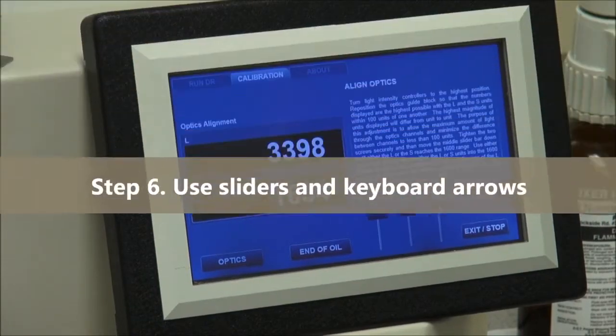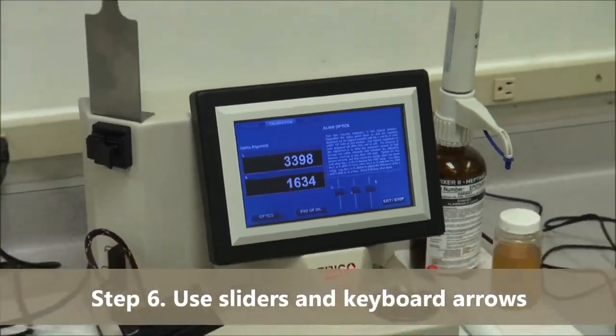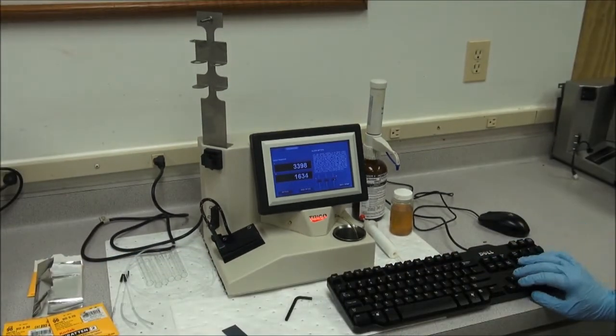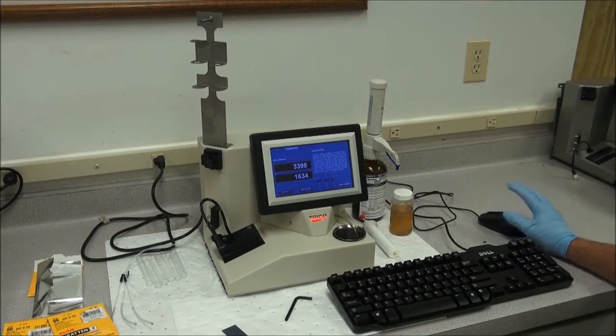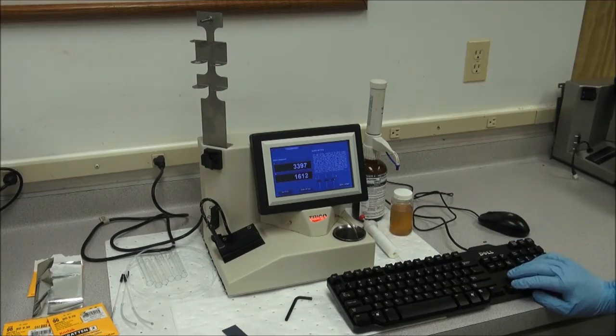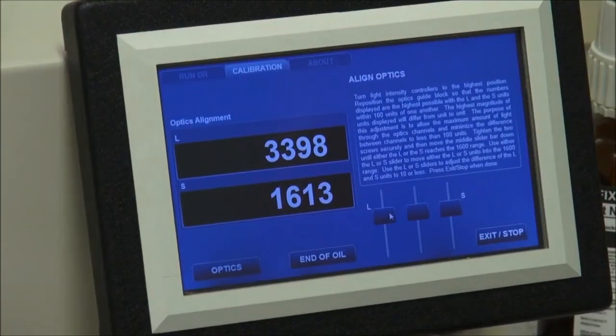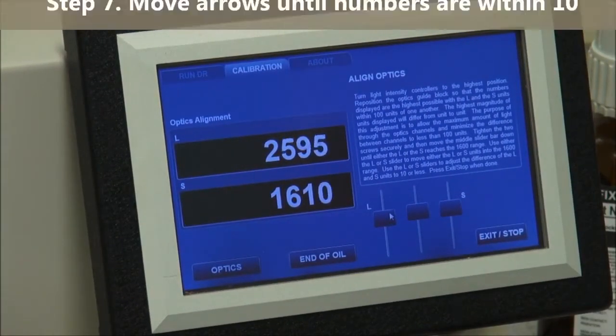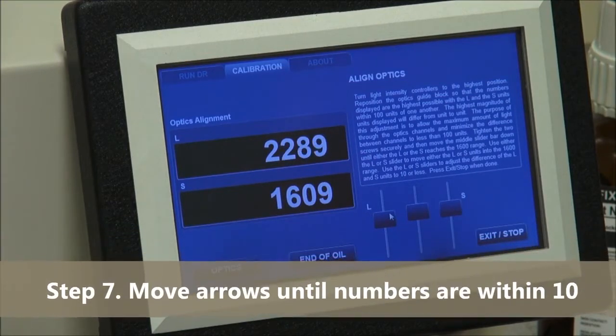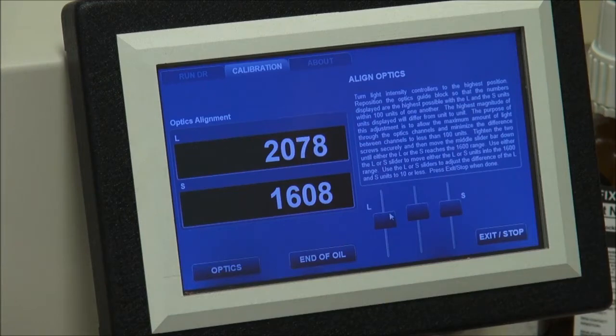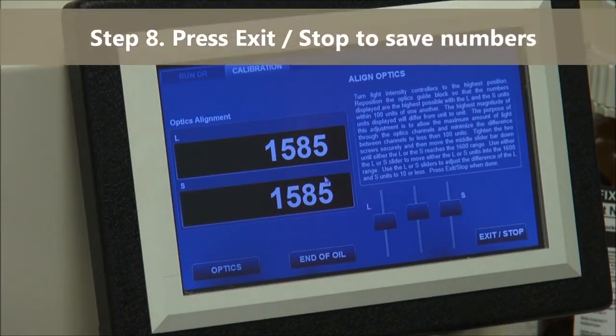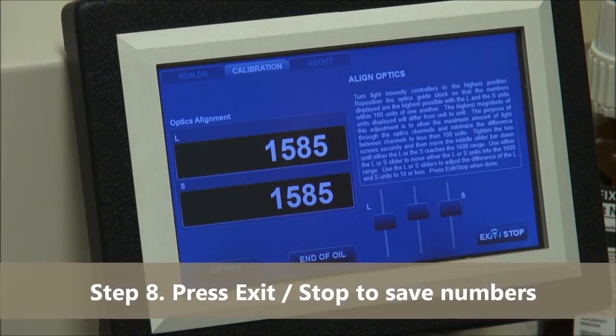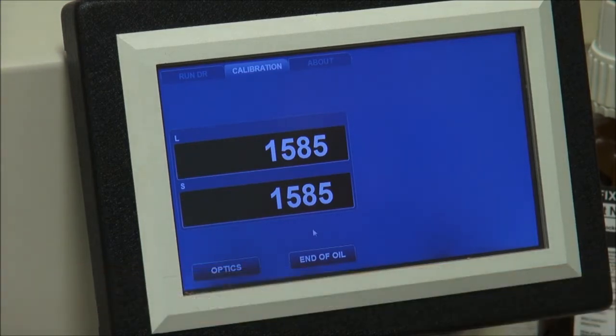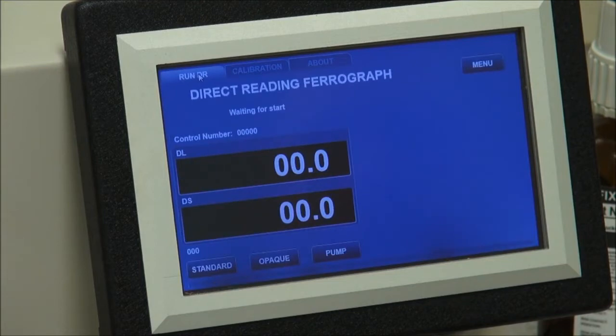Once the L or the S are in the 1600 range, use the left or the right slider bar and the keyboard up and down buttons to adjust with finer adjustment. Move each button until the L and the S numbers are within 10 of each other. Once both are within the 1600 range and within 10 of each other, press exit and stop to save your numbers. Go back to the main screen by hitting the Run DR tab in the upper left. You're now ready to run a test.